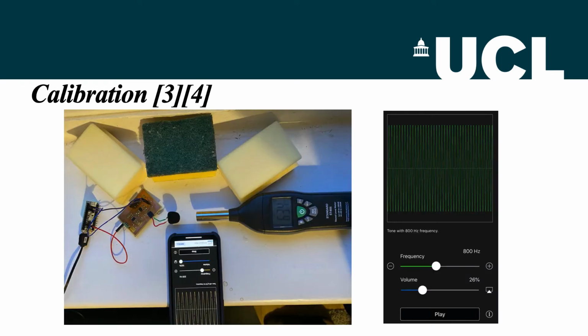Next is the calibration of the device. The picture shows the calibration process of the device. The process is done in an open field. The sponges or absorbers also make sure only very little sound is reflected to affect the result. The device is put at the same level as a reference SPL meter, which has a 30 dB to 130 dB measuring level range from 31.5 Hz to 8000 Hz.